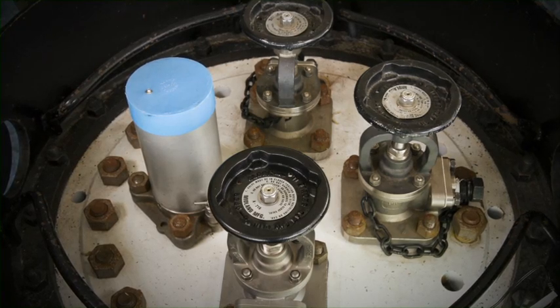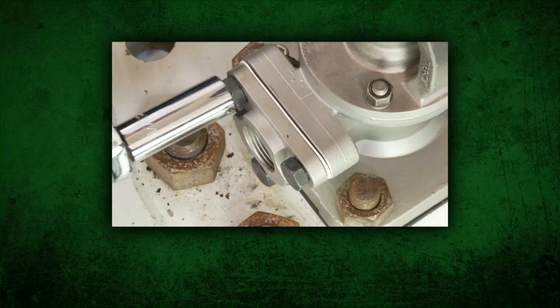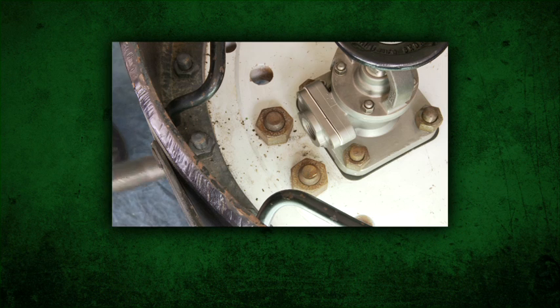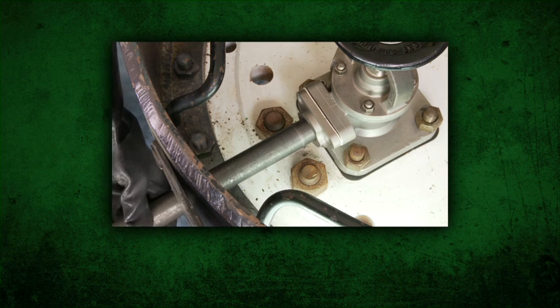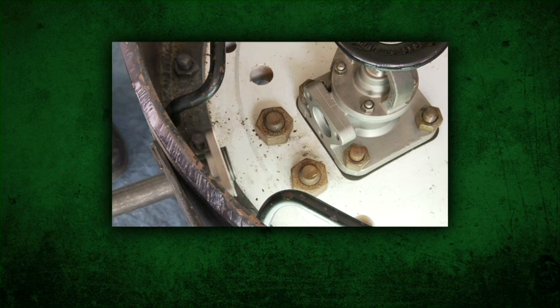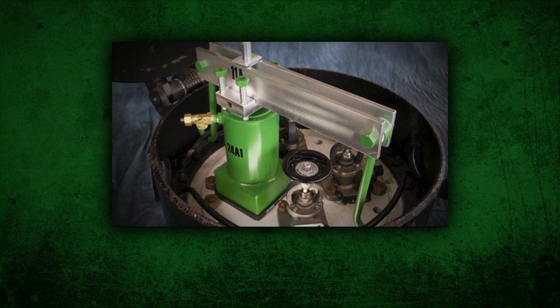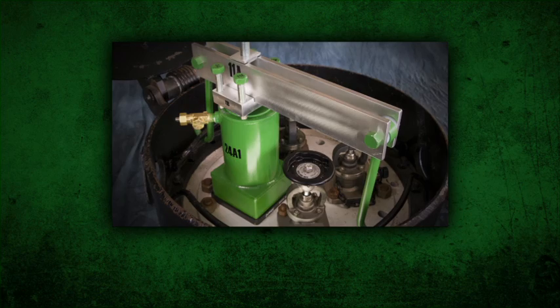To install the device over some of the newer dual valve cars, an additional step is required. Loosen and remove the three cap screws securing the valve outlet flange to the valve body. A one-inch threaded stabber pipe needs to be inserted through the housing port near the leaking valve. Thread the pipe securely into the valve outlet flange. Tap the stabber pipe on the sides with a hammer until the valve outlet flange is loosened. Remove the stabber pipe with the outlet flange attached. Hood 6A1 cannot be used on these valves; instead, Hood 2AA1 must be used.